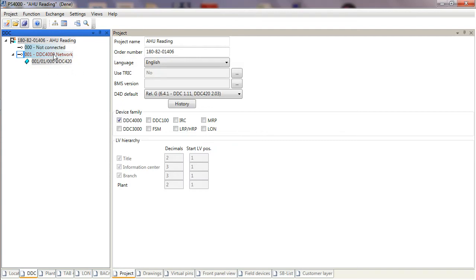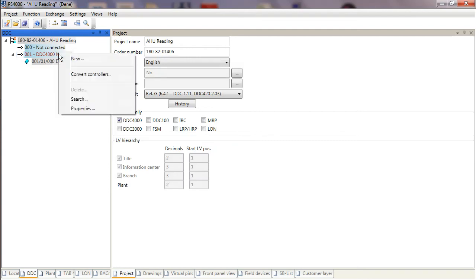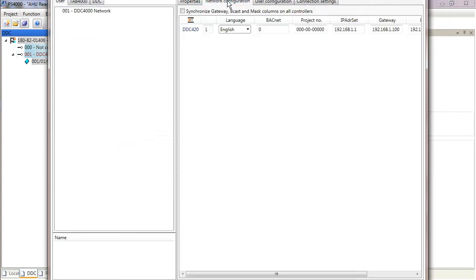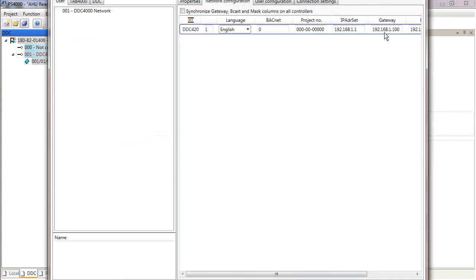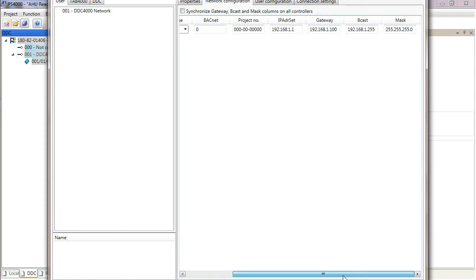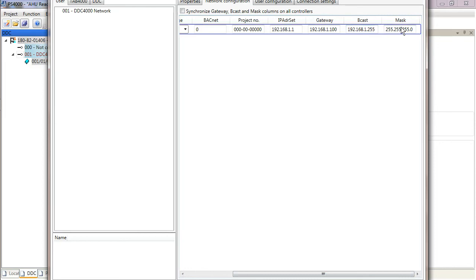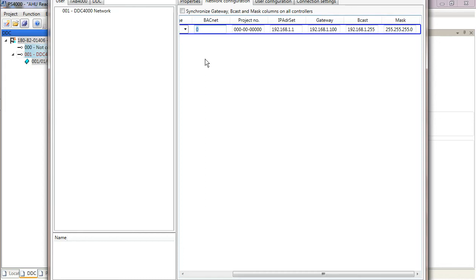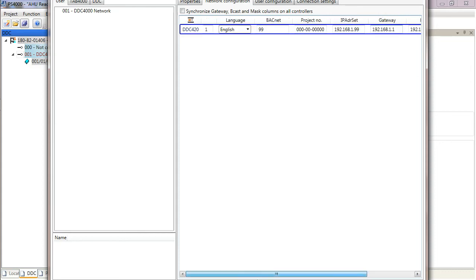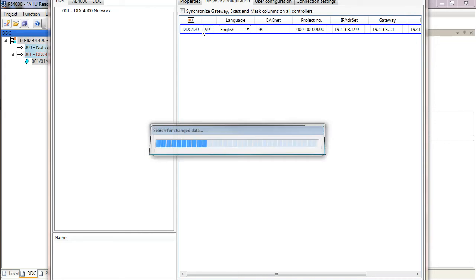It's very important at this stage if I set up my network properties. I choose Network Configuration and I allocate my IP address, the gateway, and also the broadcast, which follows the same IP range but ending in 255. I can set up a subnet mask and a BACnet ID for the controller. Let's say this is going to be BACnet address number 99, IP address 1.99, the gateway is 1.1, broadcast is 1.255, and the DDC address is going to be 99. I can just say Okay to that.